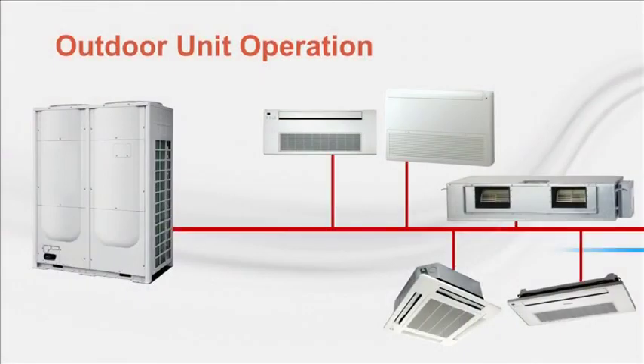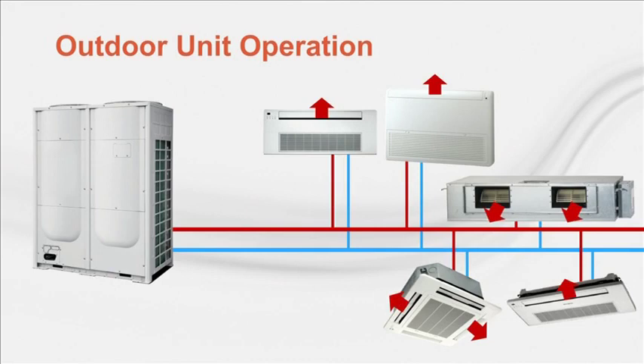During cooling operation, refrigerant is compressed by the machine's compressors within the outdoor unit. The hot, high-pressure refrigerant passes through the heat exchanger, which is currently running as a condenser to reject heat. The refrigerant is then distributed to the indoor expansion devices and evaporators to remove heat from the spaces. During heating operation, heat pump VRF systems reverse their cycle and refrigerant flow to provide heating. In this mode, the hot, high-pressure refrigerant is sent to the indoor unit heat exchangers, which serve as condensers. Heat is added to the spaces. The refrigerant then flows to the outdoor unit, passes through an expansion device, and through the outdoor coil.